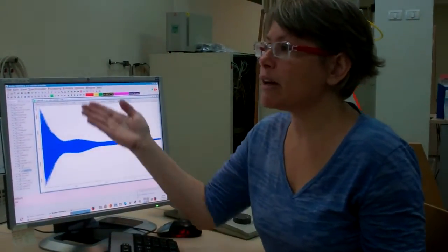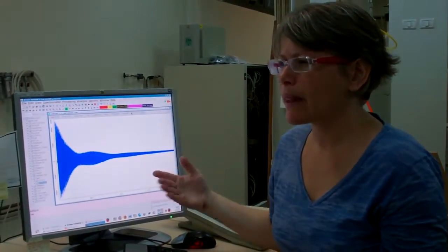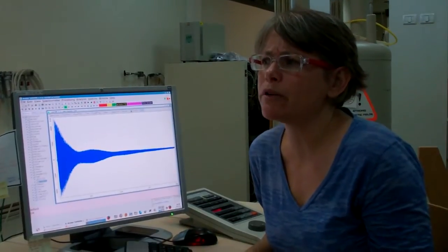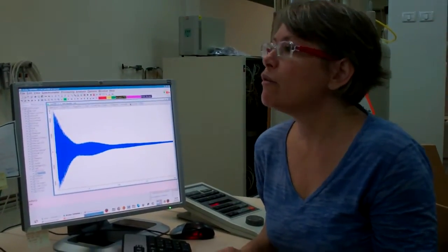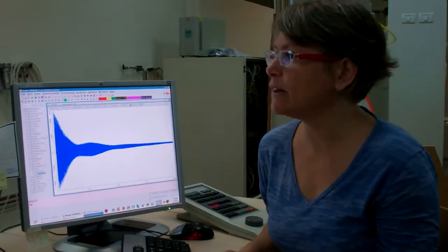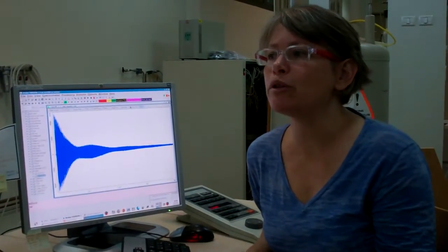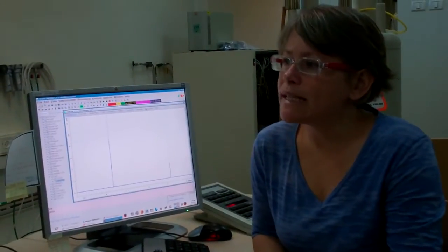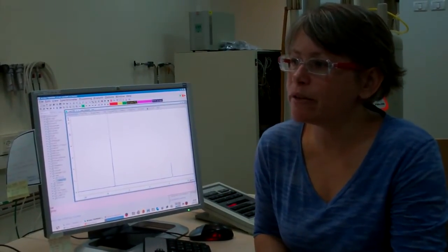The time domain, the FID, is a plot of intensity versus time. How do we get our proton NMR spectrum in the frequency domain, which plots intensity versus frequency? We'll request the computer to perform a Fourier transform. We'll go over the NMR processing in detail in the next video. Here, our primary goal and interest is in optimizing the acquisition parameters.